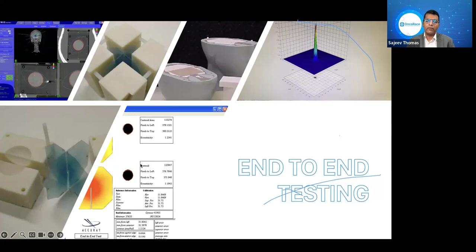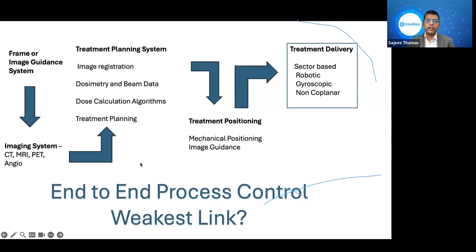If you look at radiosurgery, this is a chain of procedures that starts from localization, treatment planning, treatment positioning, and treatment delivery. So the weakest link in this whole procedure is going to define the accuracy of the whole procedure. End-to-end testing in radiosurgery, also known as end-to-end quality assurance, involves verifying the entire treatment process from localization and planning to delivery, to ensure accurate dose delivery to the target. This includes evaluating geometrical accuracy, dose distribution, the overall functional integrity of the treatment planning system, etc.